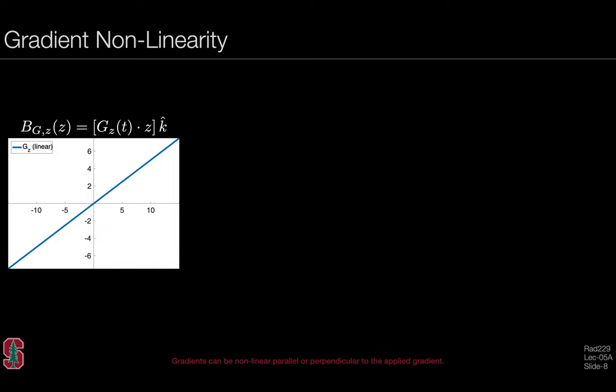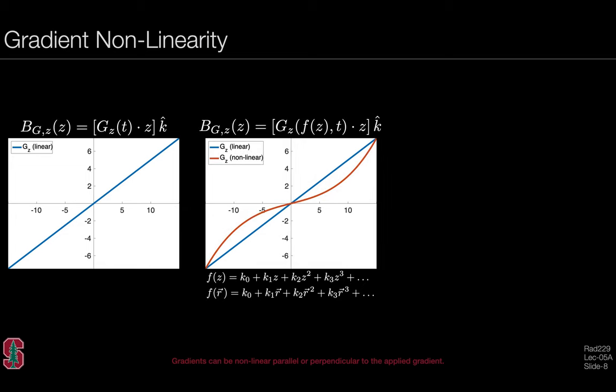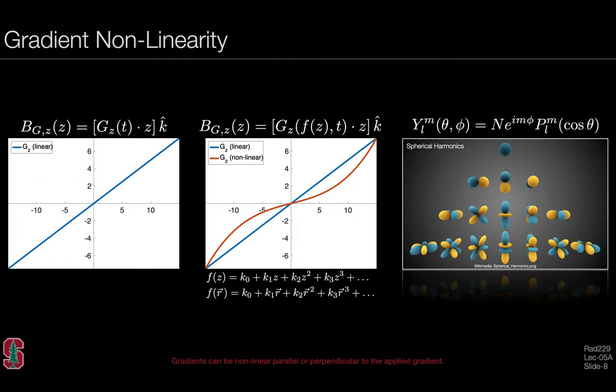What happens in the context of gradient non-linearity? If we have non-linear gradients, we have a different mapping of magnetic field strength as a function of position. Here we've introduced a new term where the Gz gradient depends on some function of space as well as time. Now the map has a different frequency to space mapping that may have some curved form, a quadratic function, cubic function, or expressed in some other way.